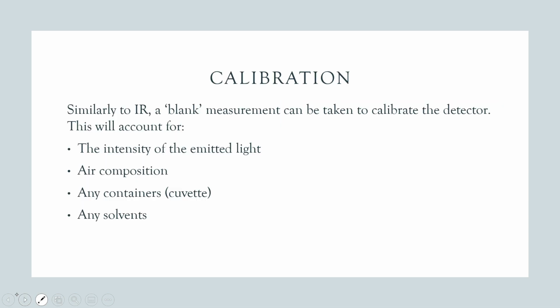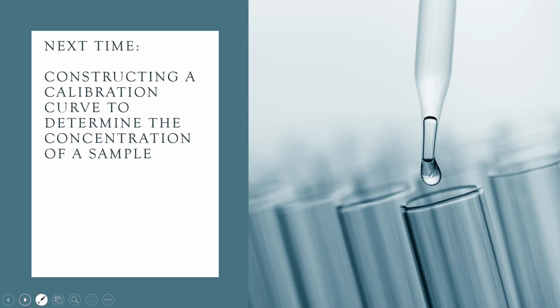Last thing to keep in mind is the concept of calibration. It's really similar to IR. You generally take a blank measurement first. What that means is the light is passing through the air and whatever air composition you currently have in your lab at the time. It passes through the container that's actually holding the sample, and it will pass through the solvent as well. And that blank measurement will ensure that the machine itself knows exactly how much light can pass through without the substance. And then when it's taking those absorption measures, it actually measures the absorbance of the substance and nothing else.